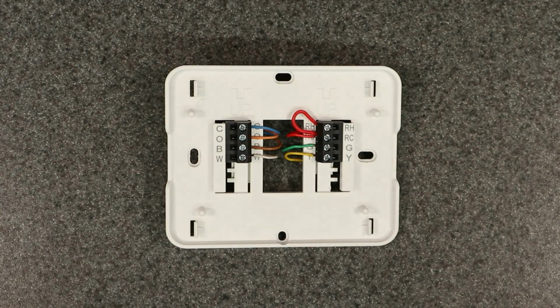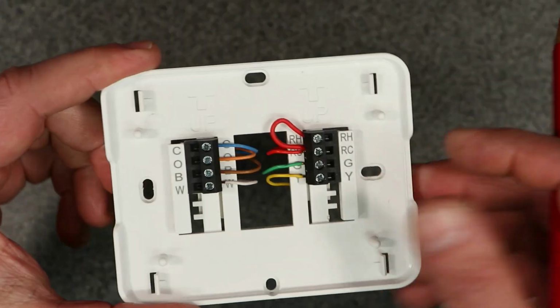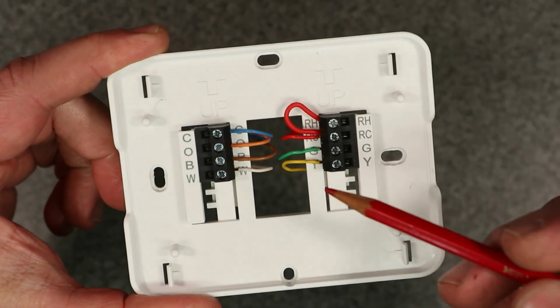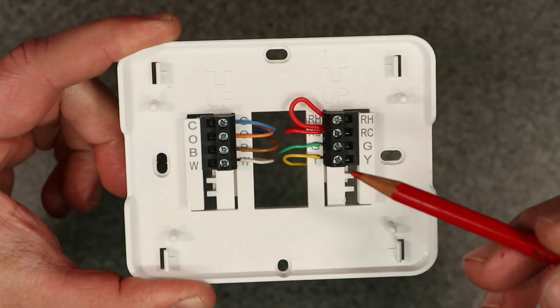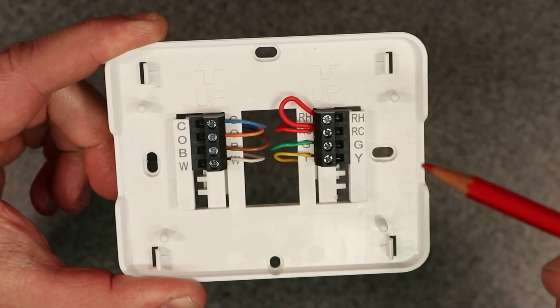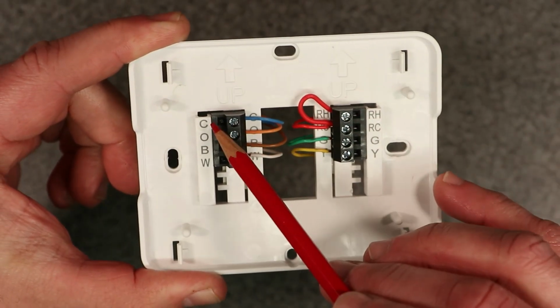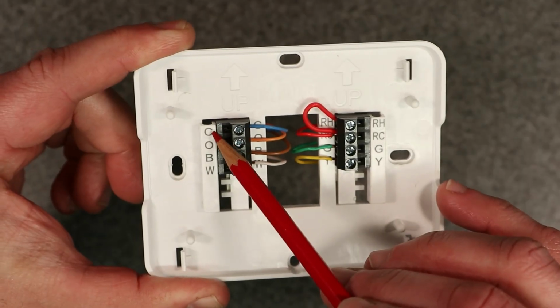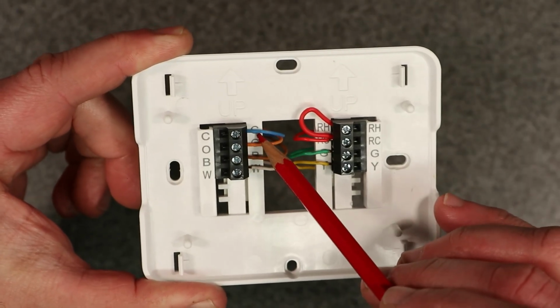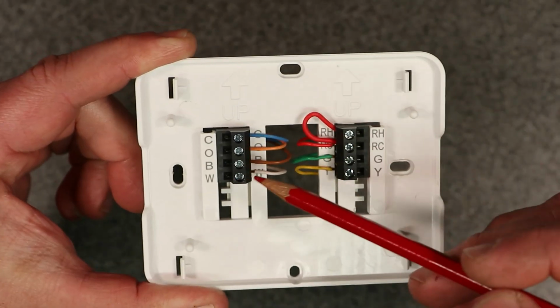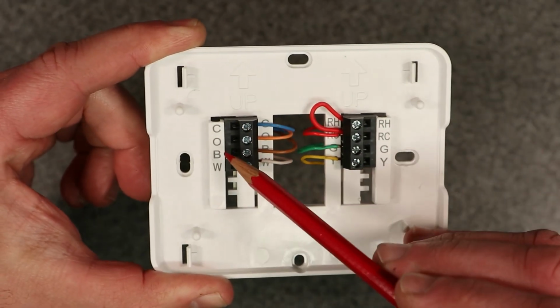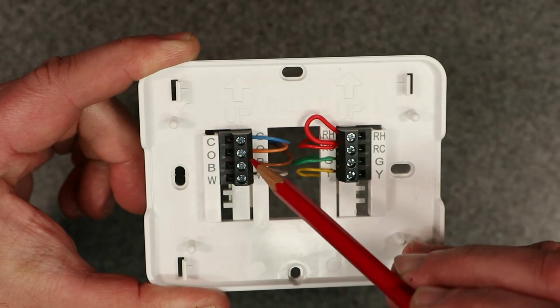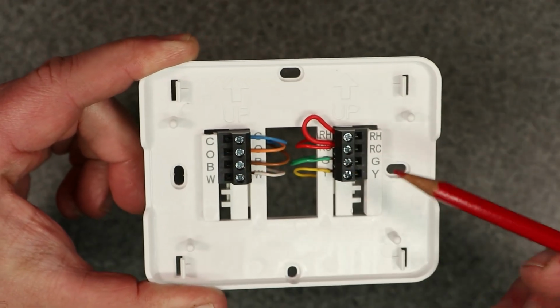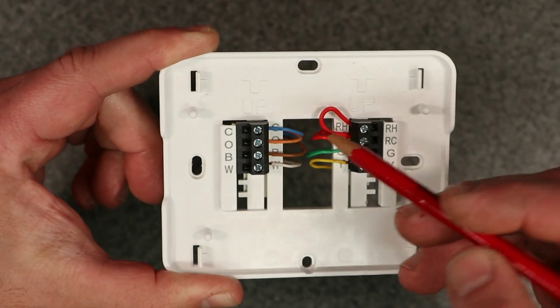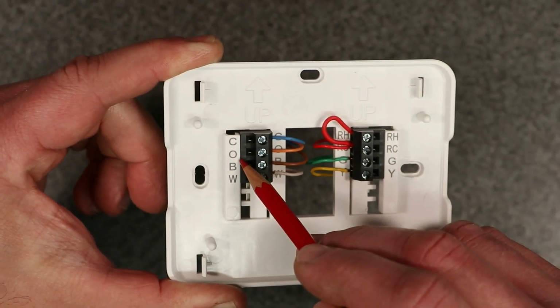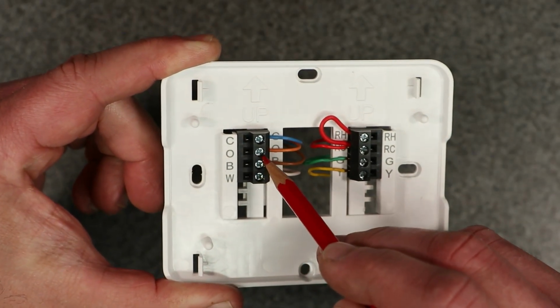All right, so let's move along to the base plate and check out the wiring. Now I'm going to go really quick over the wiring, what each one kind of signifies and what it does. I'm not going to go into too big of a detail, but let's start at the left side here. We're going to have the C terminal, which is the common wire. That's your blue wire, okay? That powers up the thermostat without the batteries, okay? The O is for orange. That's for your reversing valve for the heat pump, if you had a heat pump hooked up to this. Reversing valve for the cooling, okay? That's what the O stands for.